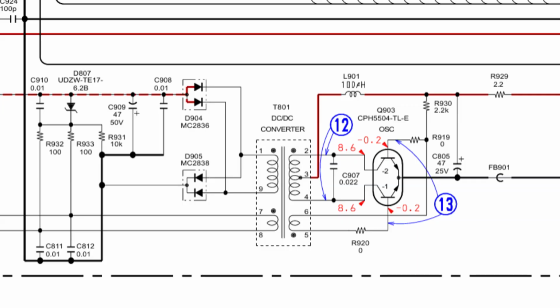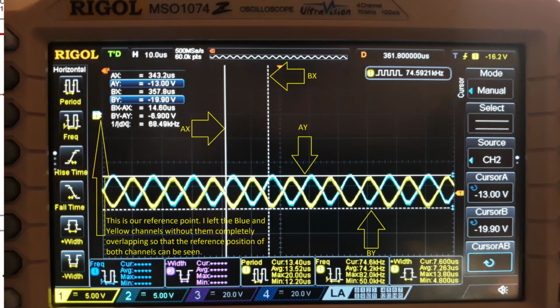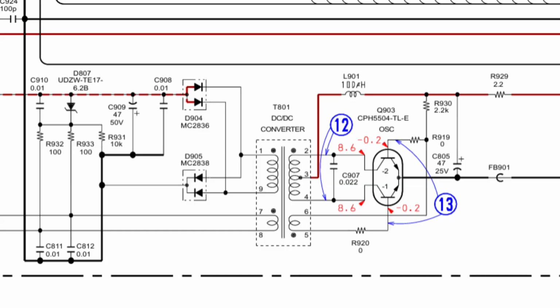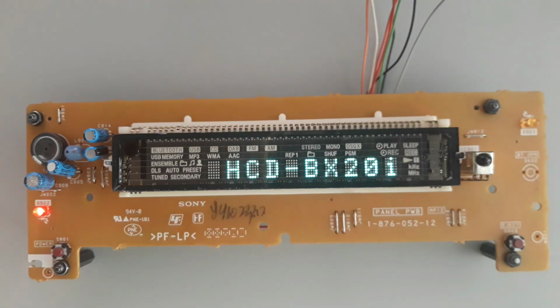On the secondary side, the transformer provides AC voltage for the filament through pins 7 and 8. The VE voltage is generated separately through a full-wave rectifier connected to another winding, using pins 1 and 9. The filament reference is then established relative to the VE supply, ensuring that the filament operates at the correct negative potential.